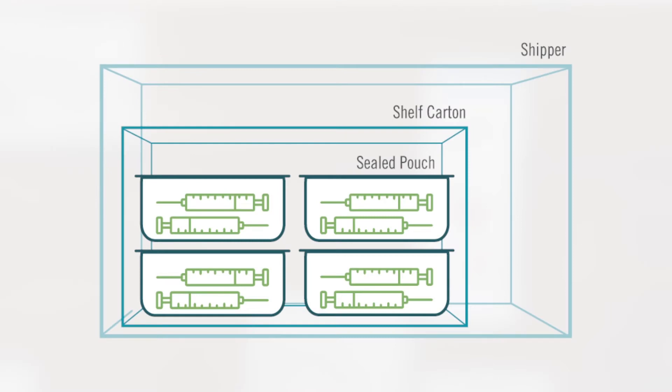Commercially available PCDs mimic multiple packaging layers by using an innovative biofilm. The ETO gas must permeate through the film in order to validate the sterility of the load.